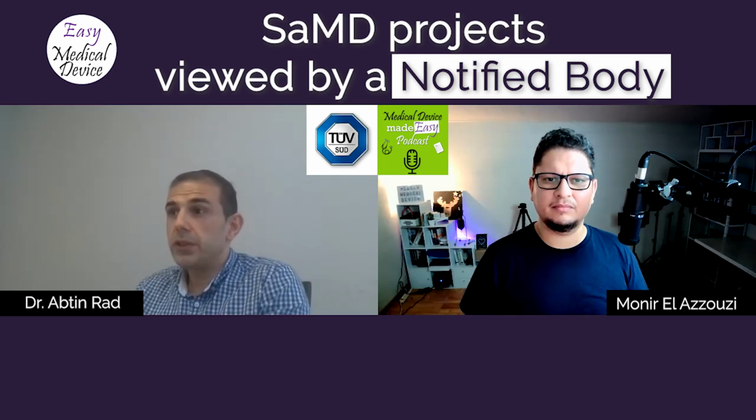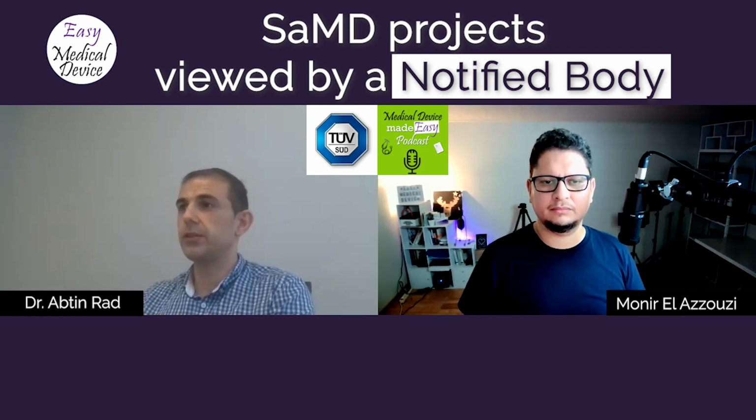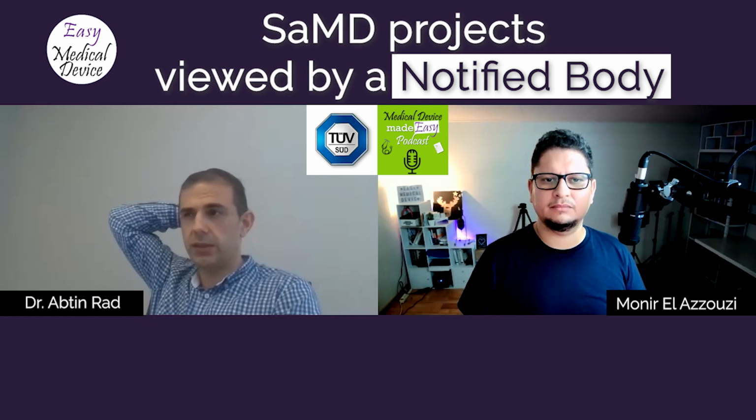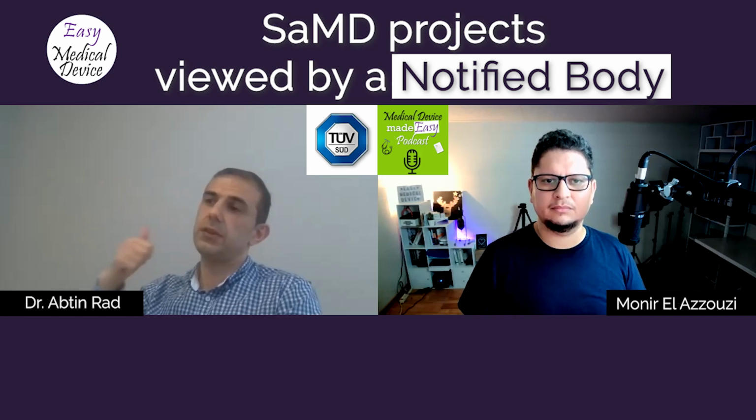So one day the regulators identified that cybersecurity in medical devices is an issue, so they needed to include it in the regulation, forcing the manufacturers to do something. And they came up with a regulation where the MDD has nothing for cybersecurity defined, only indirect requirements somewhere in the clinical aspects in Annex 9, I think, or 10. The MDR already lists 6 cybersecurity requirements in 17.4, I think 17.1, and in 23.4 you have to list the cybersecurity residual risk in the instructions for use.